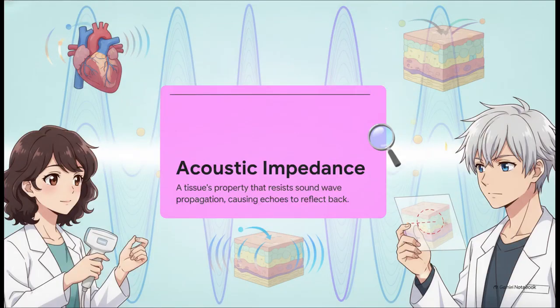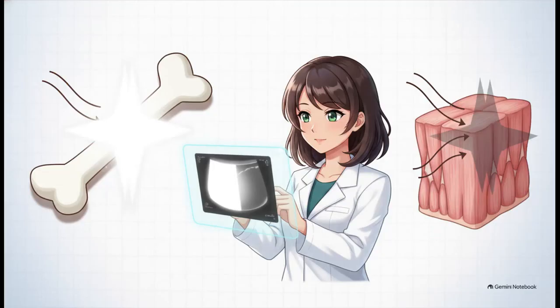Which brings us to acoustic impedance. This is basically a tissue's property that resists the propagation of sound waves. Essentially, the ultrasound machine builds its entire image based on how different tissues reflect sound depending on their density. When a sound wave hits a boundary between two tissues with vastly different acoustic impedances, a much stronger echo is reflected back to the probe. And this brilliantly illustrates how we get that contrast.